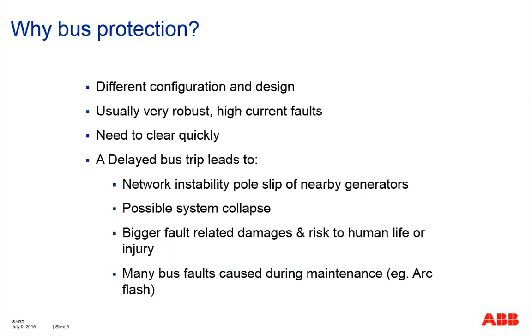Decades ago, bus protection probably was not a strict requirement for utilities. Faults on the bus usually could tolerate a certain amount of delay from backup protection, from the main equipment protection, such as transformers, such as lines. They can provide a decent, relatively fast, but with time delay, bus protection.